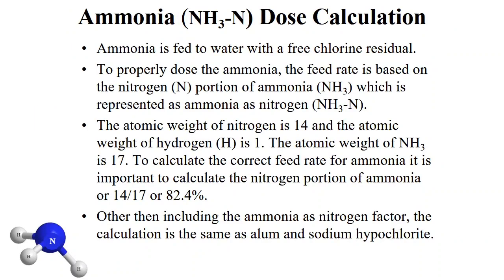Another common chemical at water treatment plants is ammonia. Calculating the feed rate is similar to alum and hypo, but there is a slight difference. Ammonia is fed to water with a free chlorine residual with the goal of creating monochloramine. The feed rate is based on the nitrogen portion of ammonia, represented as ammonia as nitrogen. The atomic weight of nitrogen is 14, hydrogen is 1, so the atomic weight of ammonia is 17. The nitrogen portion is 14 divided by 17, or 82.4%.